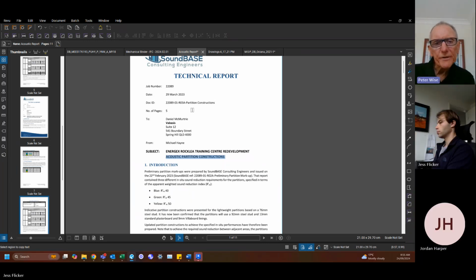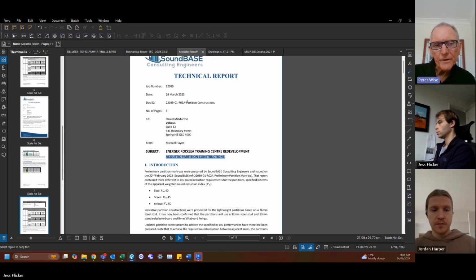In the absence of documentation, if the mechanical spec doesn't tell you what the sound levels are, you'd have to put an RFI into the system saying we've looked through the documents and can't find anything specifying the sound levels required in the various spaces. Please advise what's required. Otherwise, give them a time frame and say if we don't hear back within a week, or whatever suits you, we'll rely on AS 2107 to allocate noise levels to the spaces.